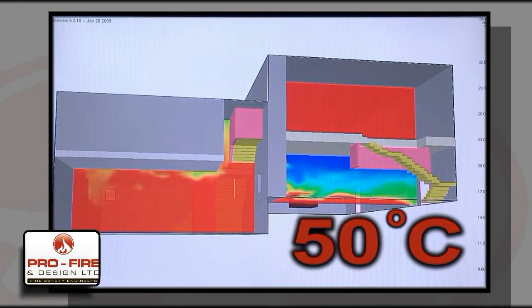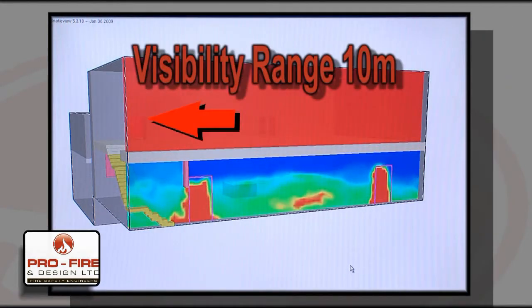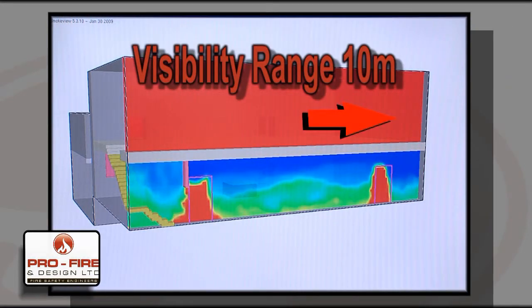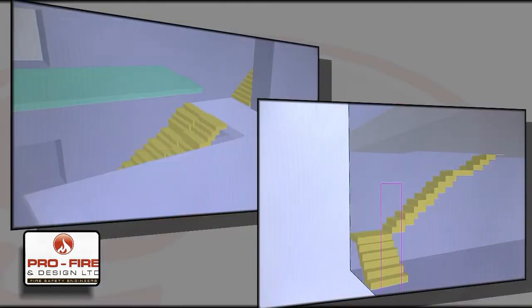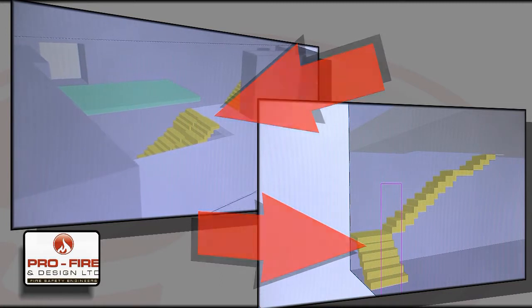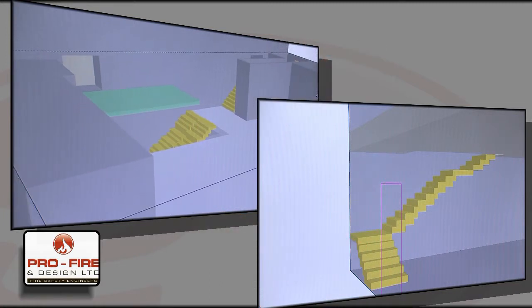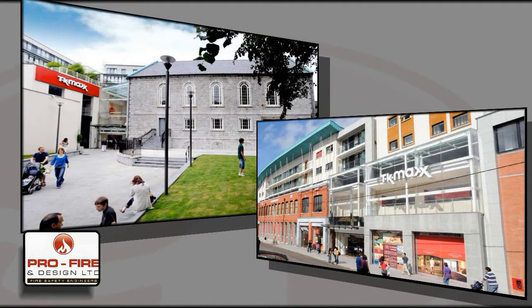This was well within the acceptable limits shown by various human behaviour studies. A visibility range in excess of 10 metres was recorded through the smoke layer. These factors were sufficient to demonstrate to the fire authority that the provision of the open stairs and lack of additional final exits to satisfy conservation issues meant the means of escape from the upper levels would remain safe.